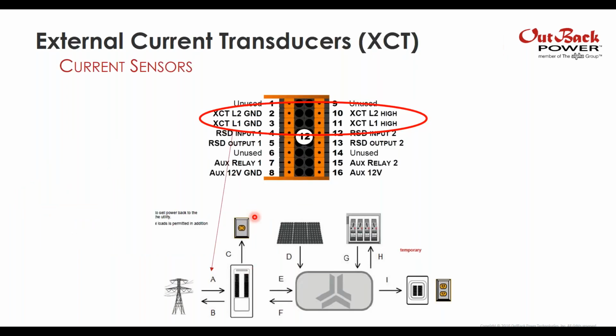If you'd like to connect external current transducers, that's easy enough to do too. Leg 2 goes to 2 and 10, leg 1 goes to 3 and 11, and then those get placed out at your main service entrance. So you buy a 200 amp CT or 100 amp CT, depending upon service entrance, and run those over to the SkyBox.